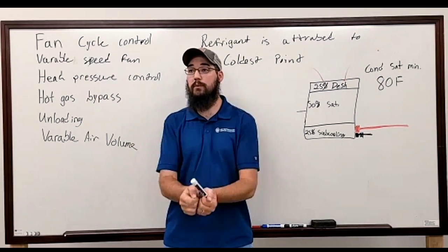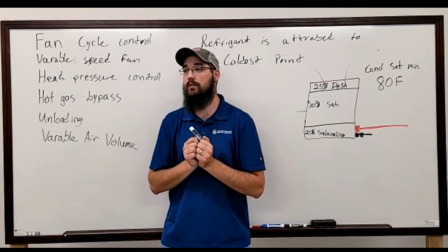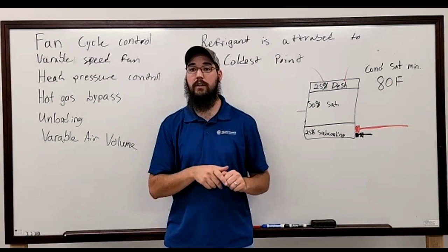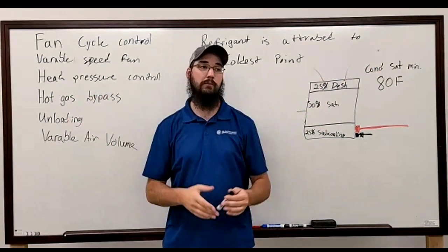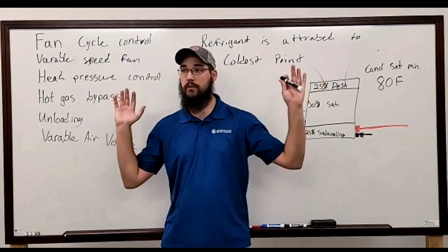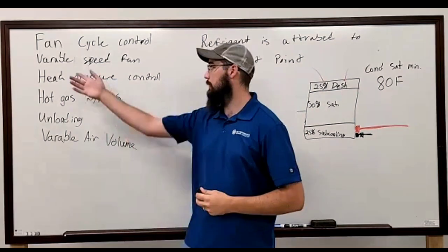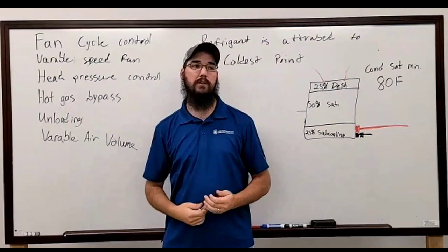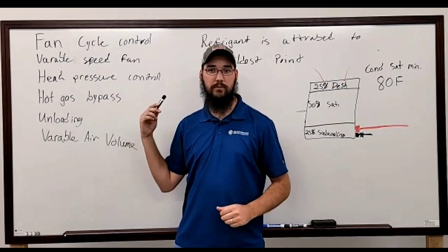in that particular scenario, we literally just removed that fan from the bus, the control bus, and capped it separately. All the other fans took off and started doing their thing, and we ordered that one fan, replaced it, got it back online, and everything was hunky-dory. But that is the world of variable speed head pressure control that we live in now. Make sense?